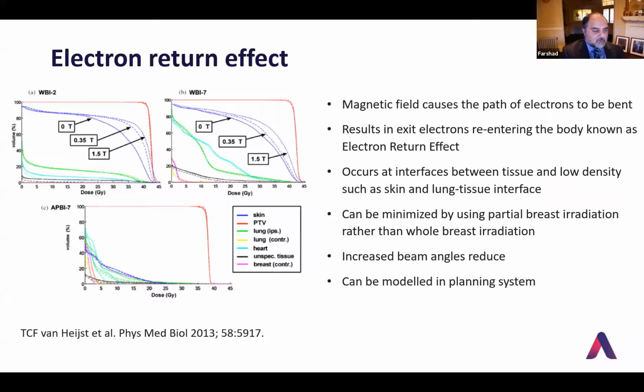Another technical thing which our planning system can take into account is the electron return effect. This is minimized by doing partial breast irradiation rather than whole breast irradiation, and also by using multiple beam angles rather than two or three, and as I say, can be modeled.